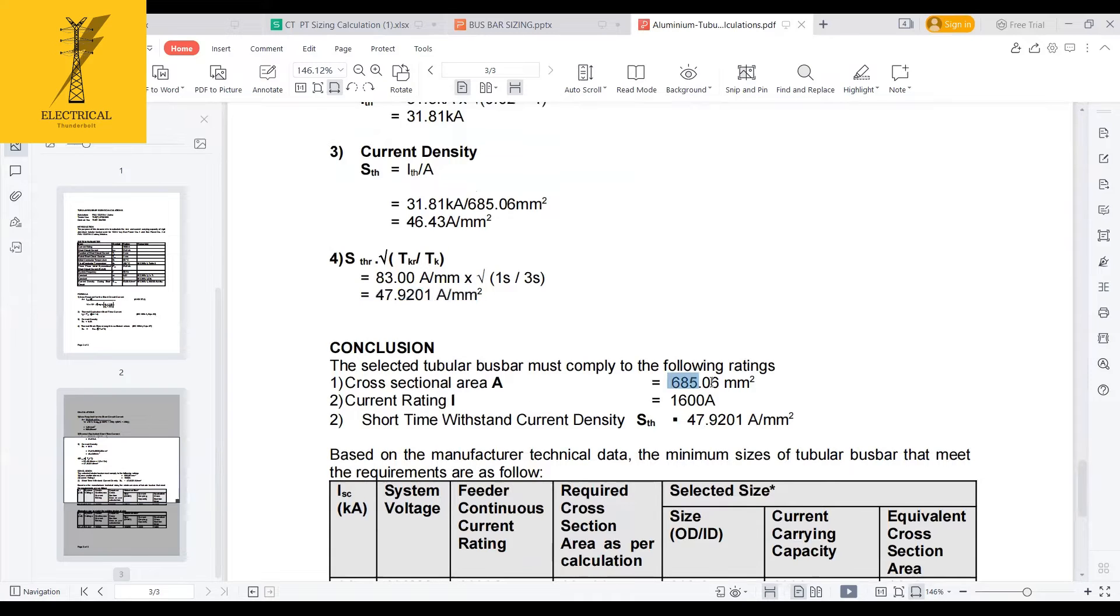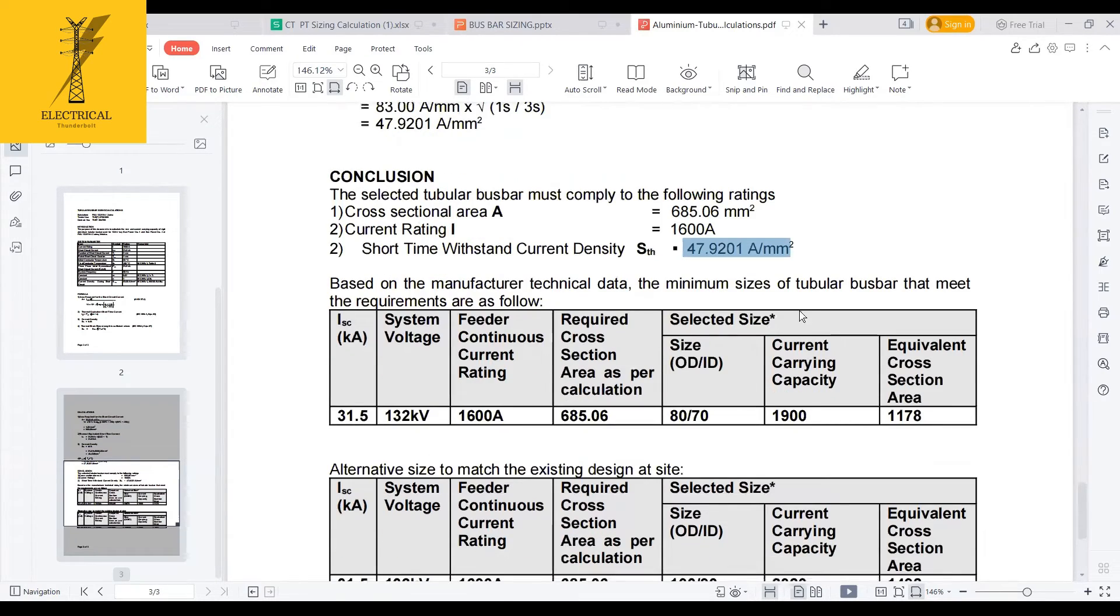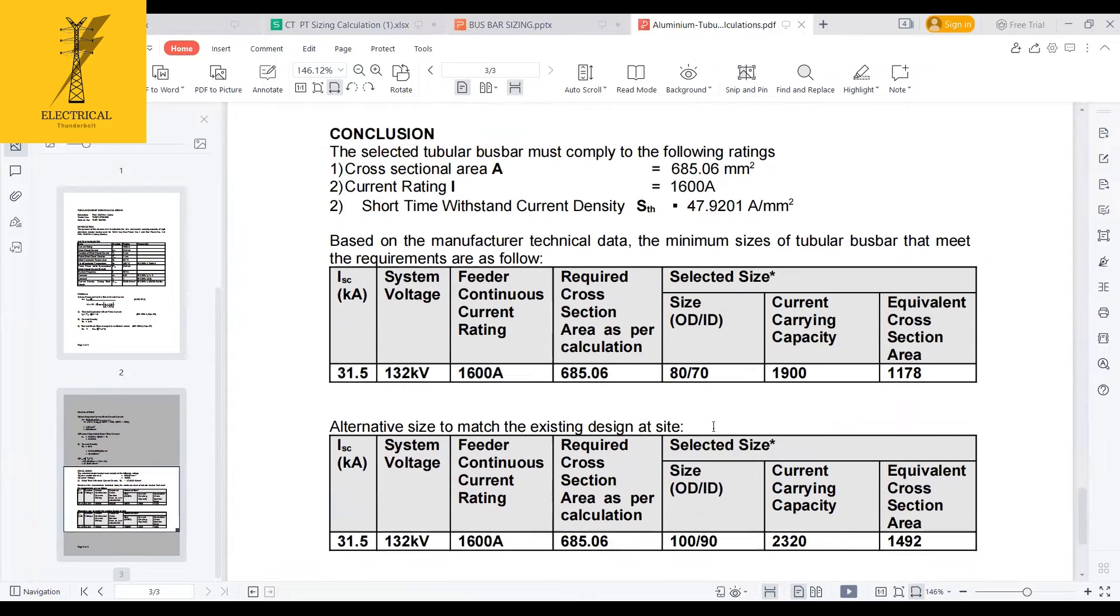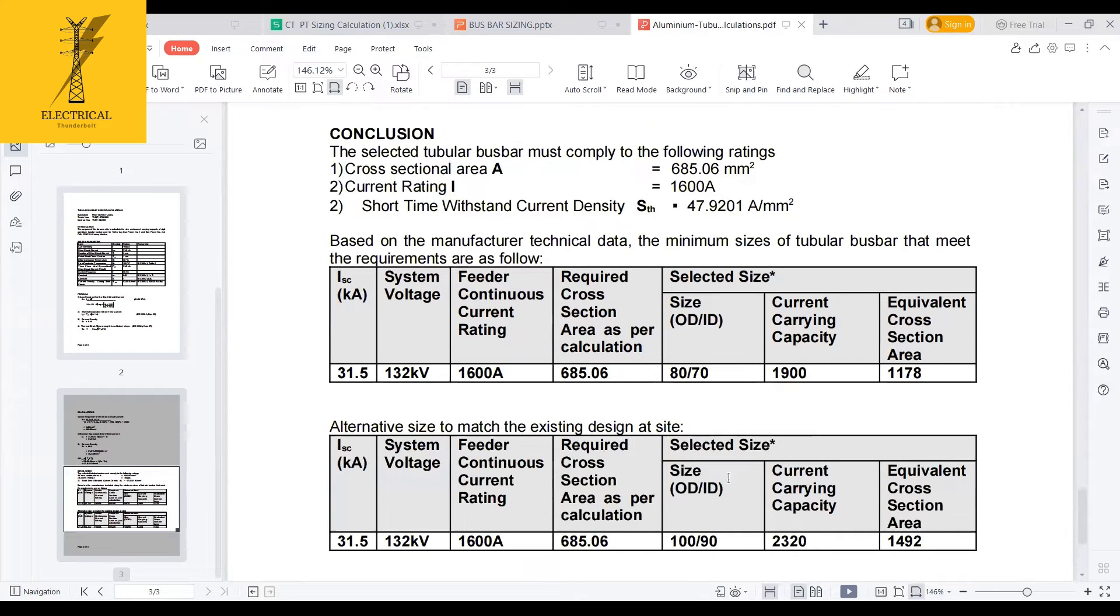So the cross-sectional area required and the current rating is sufficient is 1600 amps, and the short time withstand current is 47. So based on the manufacturer technical data or catalogs, I recommend that minimum size of the tubular bus bar, which is meeting these requirements, is this: outer diameter of 80 and inner diameter of 70. Alternate size to match the existing design at site can also be having this. This is the selection of my conductor only. Any doubts in this stream? Clear?